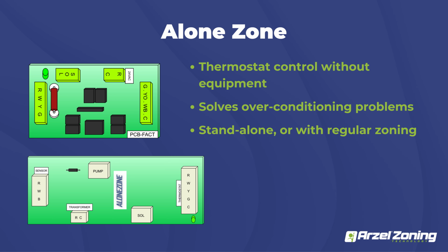Also, with either of these, you can have them built in their own individual panel. So maybe you've got a customer that doesn't really need zoning. They maybe only have one area in the home that's constantly over conditioned. You can actually just zone that one individual area with the alone zone or the Fact board. And that would give you that thermostat and damper operation to be able to close that area off when it starts getting too hot or too cold based on the temperature. It would close those dampers and prevent air from going into that area. So it's a really nice feature. It could be built in its own or in a panel box.